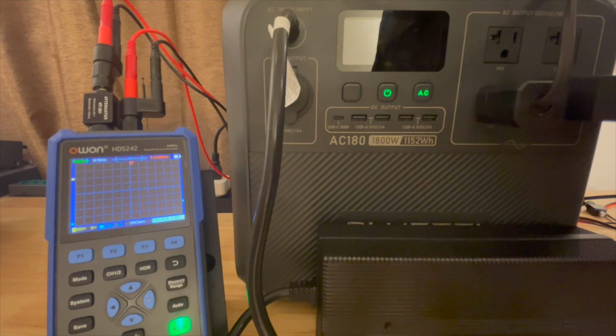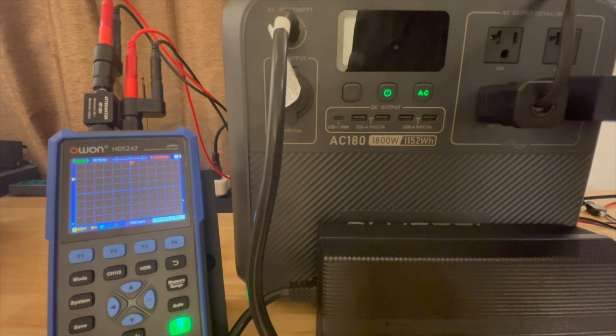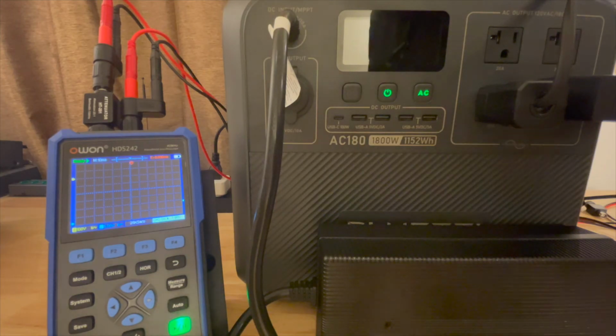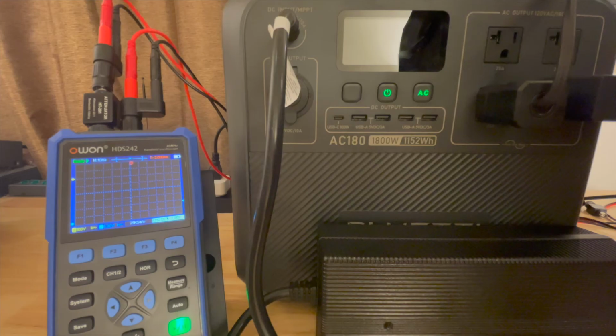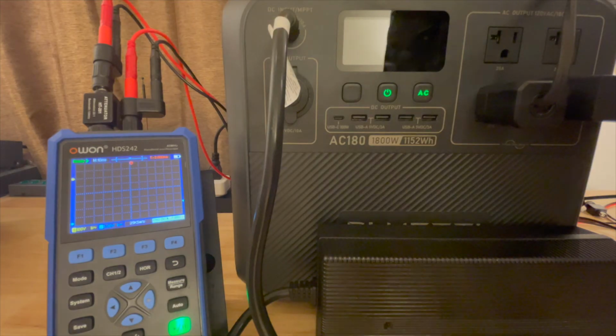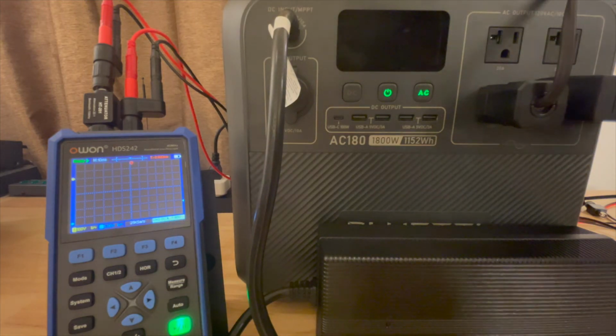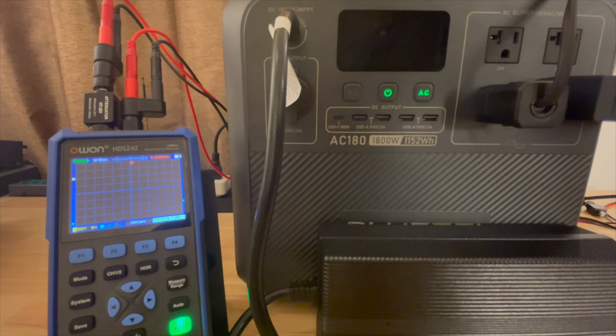So what's happening here when the power is cut? When the power is cut, the battery's charger just stops charging the battery. The load is already running off the inverter, so in theory there should be no switch time. The downside of this type of UPS system is that you're always running off the battery, meaning you're always cycling it and putting load on it. But it does mean your load is not going to lose power, so it's a more reliable system.